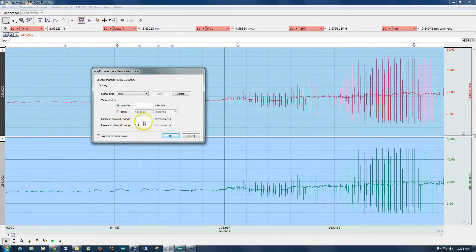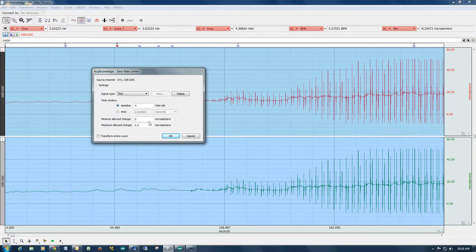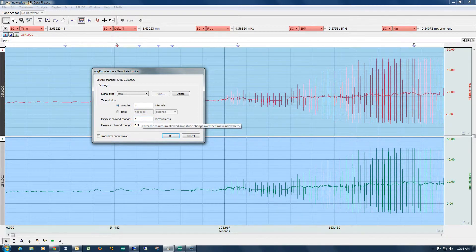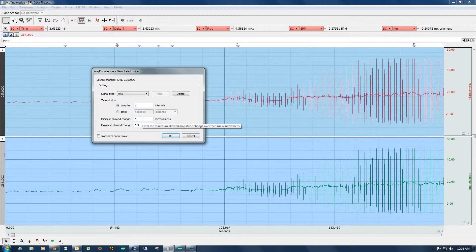Down below, you have to determine your minimum and maximum allowable change in the signal. So because this is a slow moving signal, I'm going to leave the minimum change to zero. That means that within any full sample period, you can have no change in the signal. But then at the other end of the spectrum, the maximum allowed change, I'm setting at half a micro siemen within that full sample window.